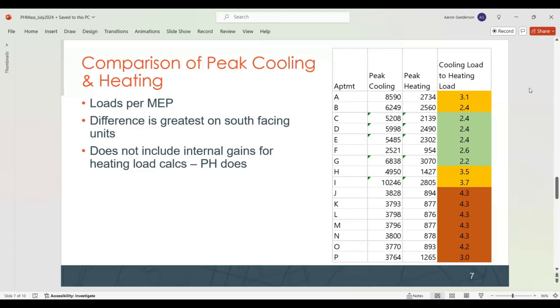And so when we actually look at these buildings, our engineering brains, that new Manual J, put in a comfort factor and make sure we oversize by this much, has to go out the window because we're actually making the buildings worse. So when you look at the way the passive house software calculates those heating and cooling loads, you have to pay more attention to those because those are actually right.